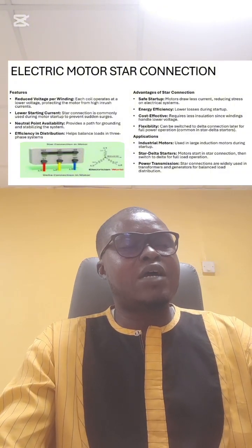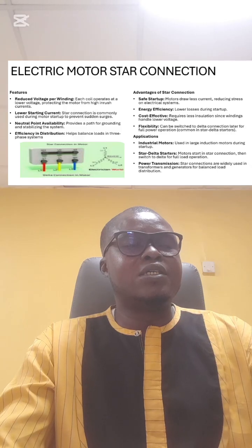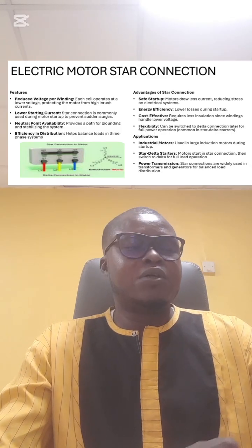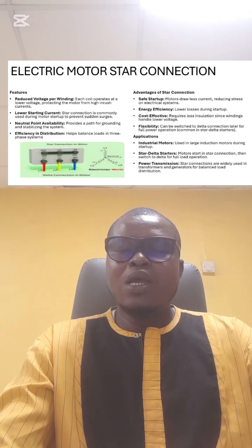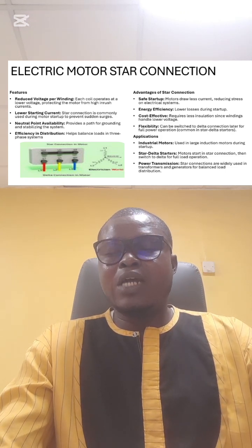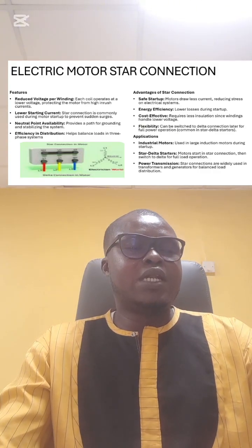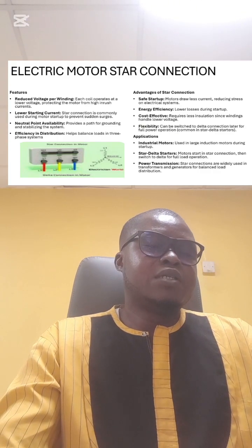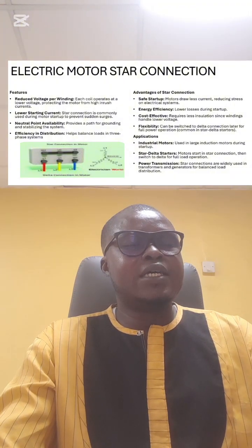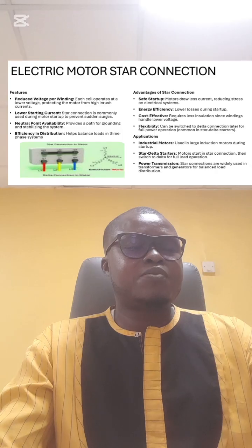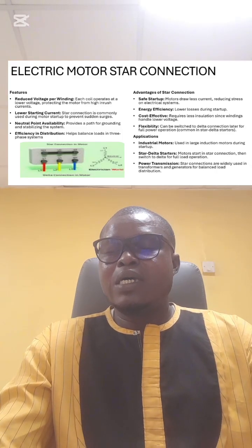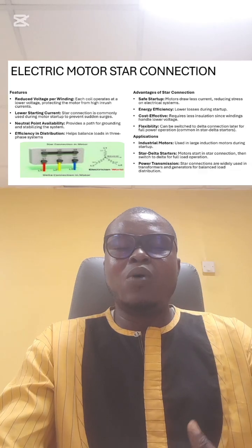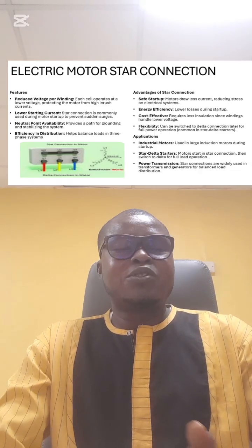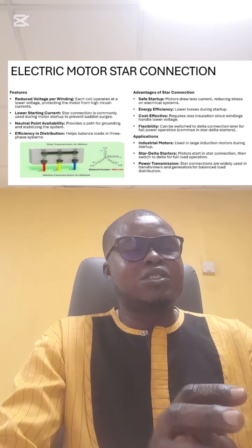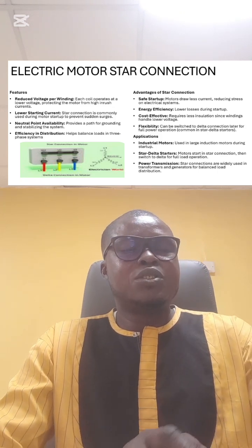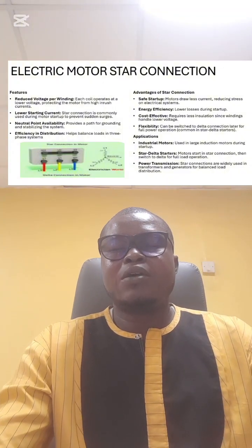One of the advantages of this star connection is safe startup. The motor draws a low current, reducing stress on the electrical system. Another advantage is energy efficiency, meaning low loss during startup. Then cost effective: it costs less for insulation since the winding handles a lower voltage. The last but not the least advantage is flexibility. It can be switched to delta connection later for full load connection.